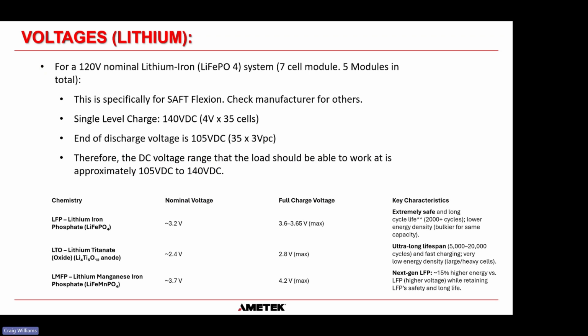And for lithium, it gets even more complicated. For a 120 volt nominal lithium ion or LiFePO4 system, which is usually 7-cell modules with 5 modules in total, we're using the SAFT Flexion model for this. Always check other manufacturers for their specific details. They're saying they have a single level charge of 140 volts DC, and then an end of discharge voltage of 105 volts DC. Therefore, the DC voltage range that the load should be able to work at is 105 to 140 volts DC, very similar to a lead acid battery.